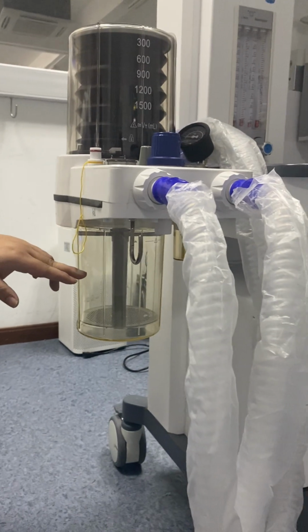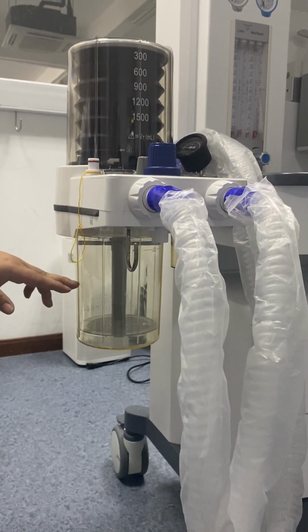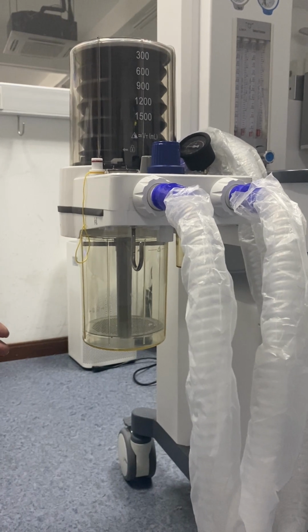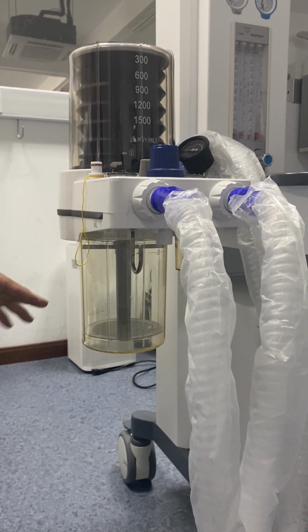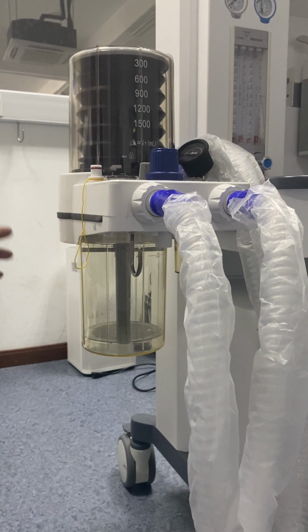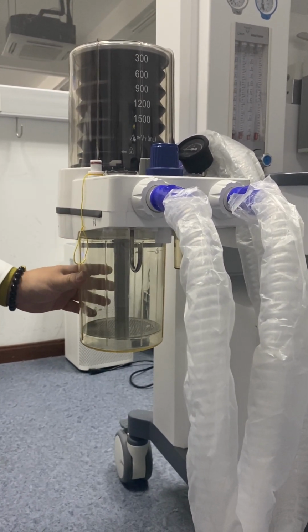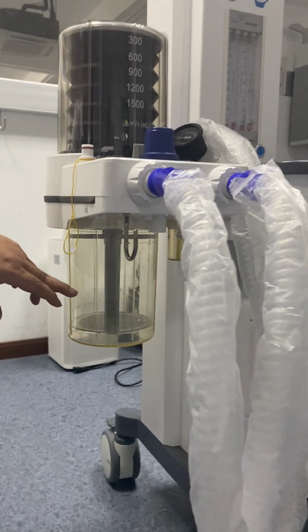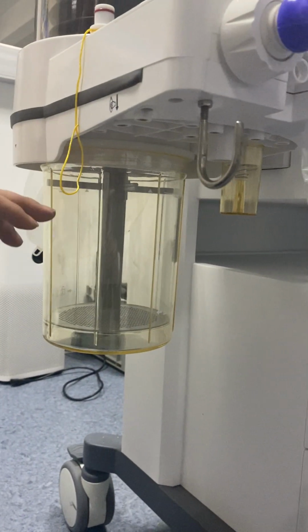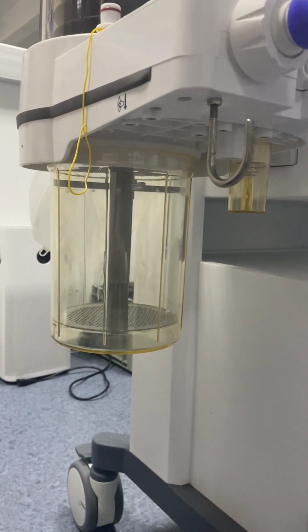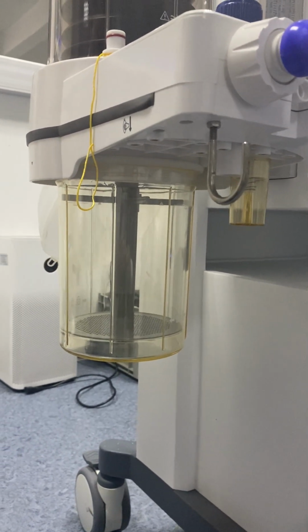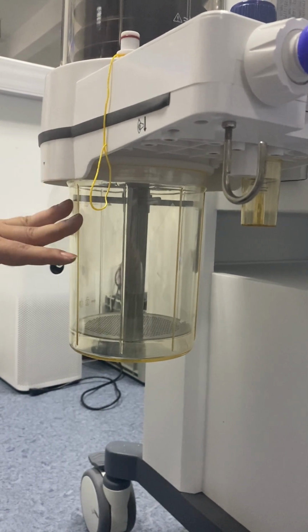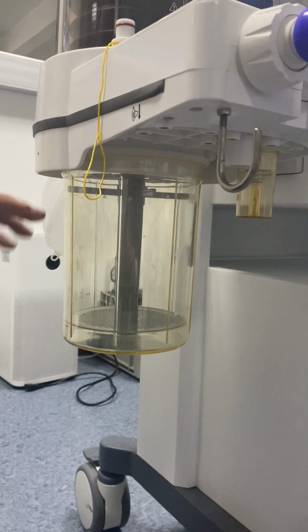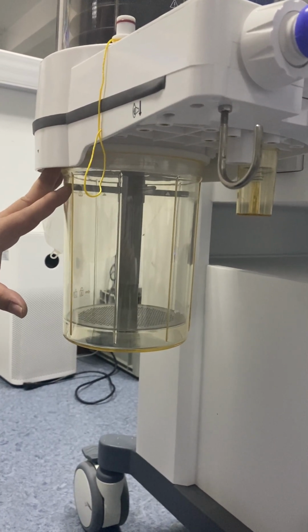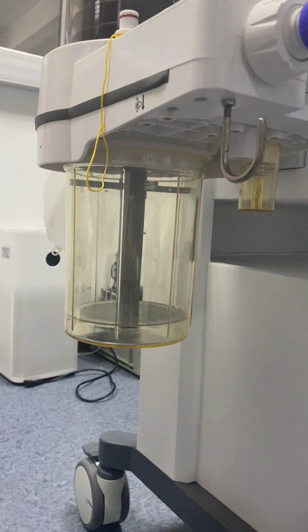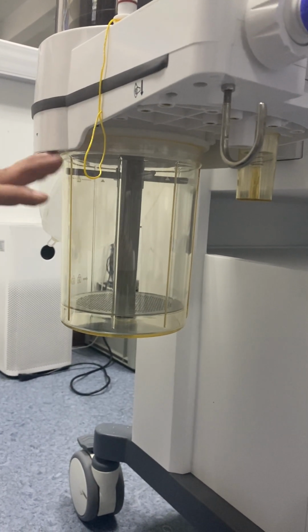For the carbon dioxide absorber, we will put the soda lime inside, and then it can absorb the water generated by the patient in the pipeline, and it can also absorb some carbon dioxide. So this is also very important. And you can see this one has a big capacity. It's 1.5 liters, which we also call 1500 milliliters. So it's a very big one, because we know some other machines maybe have only 1 liter or even 800 milliliters. If you have a big absorber, then it can ensure the operation keeps on for a long time with no need to change the soda lime.